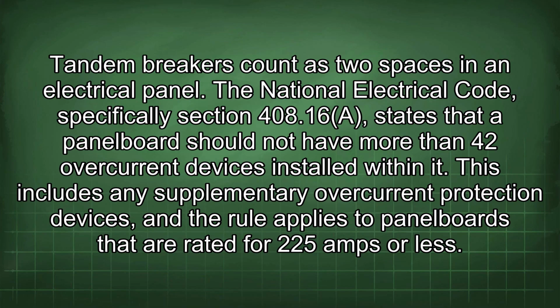Tandem breakers count as two spaces in an electrical panel. The National Electrical Code, specifically Section 408.16(A), states that a panel board should not have more than 42 overcurrent devices installed within it. This includes any supplementary overcurrent protection devices, and the rule applies to panel boards that are rated for 225 amps or less.